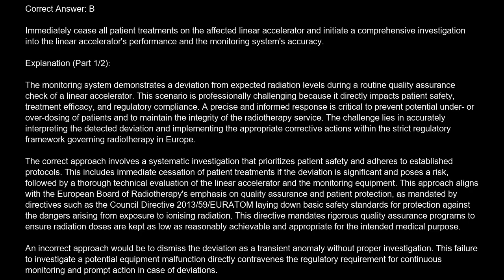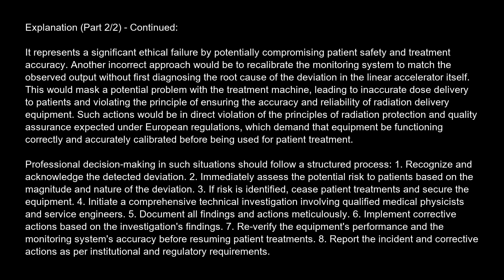An incorrect approach would be to dismiss the deviation as a transient anomaly without proper investigation. This failure to investigate a potential equipment malfunction directly contravenes the regulatory requirement for continuous monitoring and prompt action in case of deviations. It represents a significant ethical failure by potentially compromising patient safety and treatment accuracy. Another incorrect approach would be to recalibrate the monitoring system to match the observed output without first diagnosing the root cause of the deviation in the linear accelerator itself. This would mask a potential problem with the treatment machine, leading to inaccurate dose delivery to patients and violating the principle of ensuring the accuracy and reliability of radiation delivery equipment. Such actions would be in direct violation of the principles of radiation protection and quality assurance expected under European regulations, which demand that equipment be functioning correctly and accurately calibrated before being used for patient treatment.